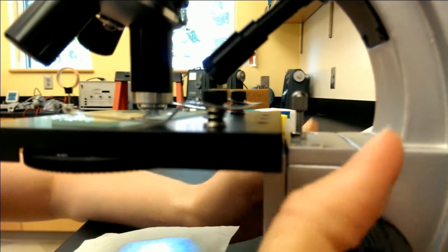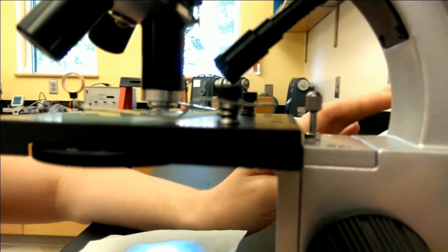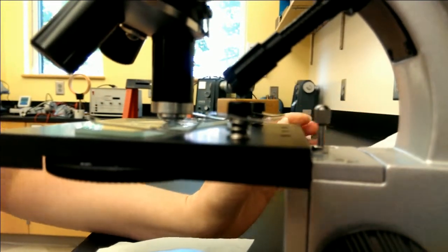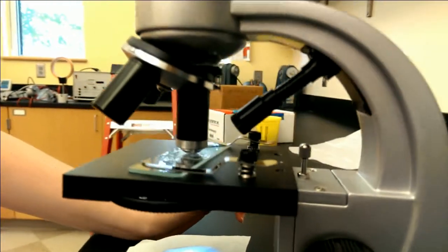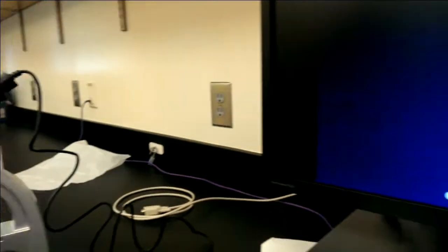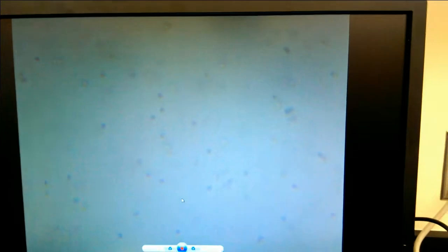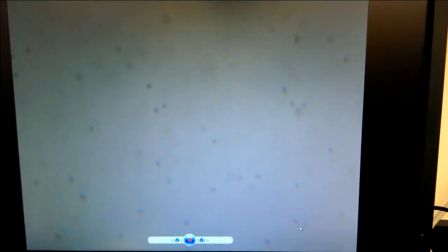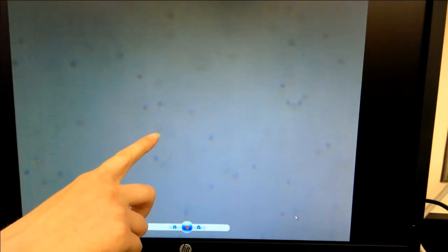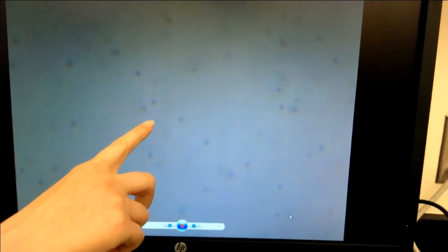And it is okay if it touches, nothing will necessarily break, there's kind of a springiness. And if you start to look up at the screen, you'll see that some of the little dots have come into focus. This is with the light all the way up. So now you can see that there's some dots. Now some dots look kind of lighter than the background and some are dark and that just has to do with how they are in the focus plane or not. So you want to kind of just make little adjustments to see how close you can get it in focus.